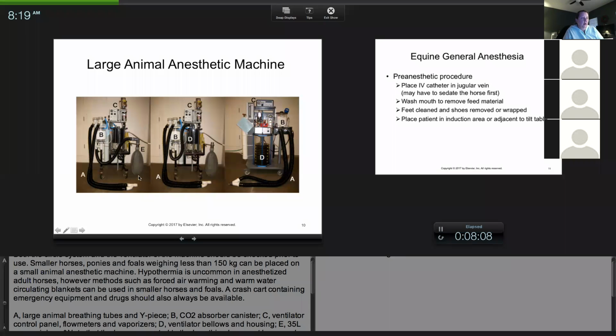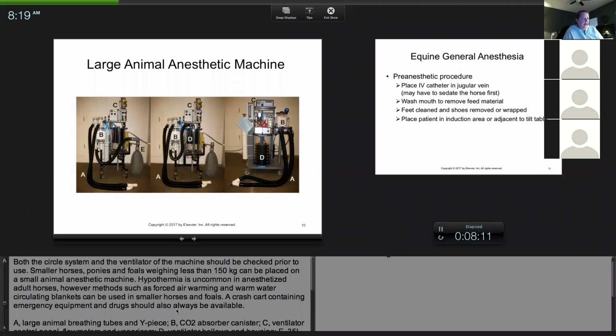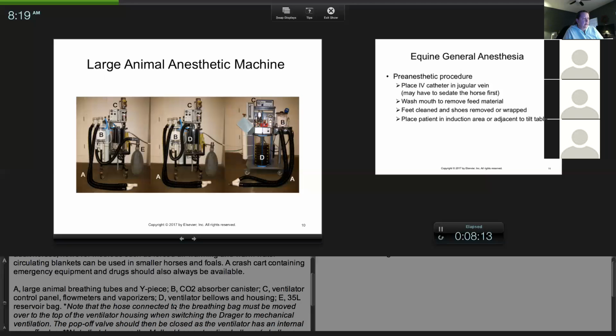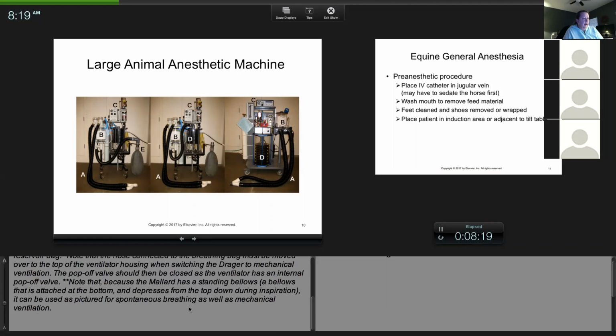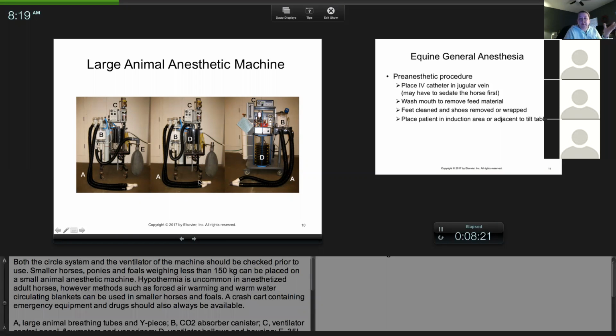And here's that very large rebreathing bag. I want to say, in this picture, if it says a 35 liter bag, but 15 liter and 30 liter bags are common bag sizes that we use in horses. So you can see how large the bag is. Letter B is pointing, that's the soda lime. So you have a soda lime canister. Obviously that's much bigger. And then letter D is the ventilator.